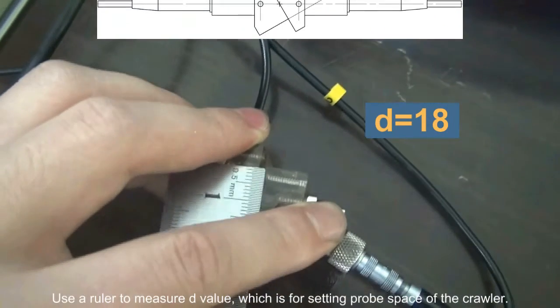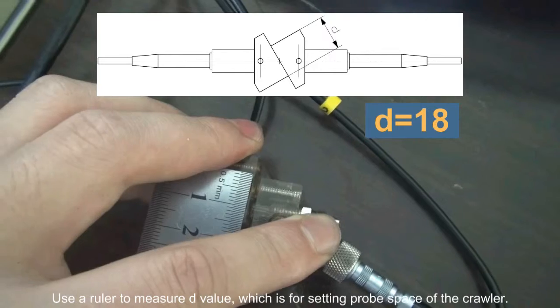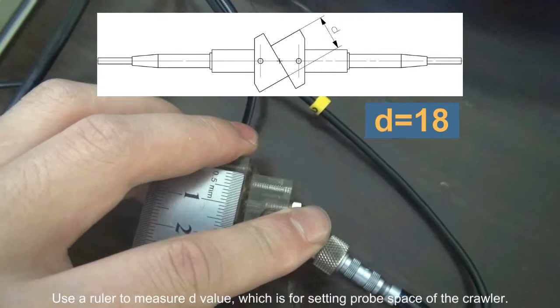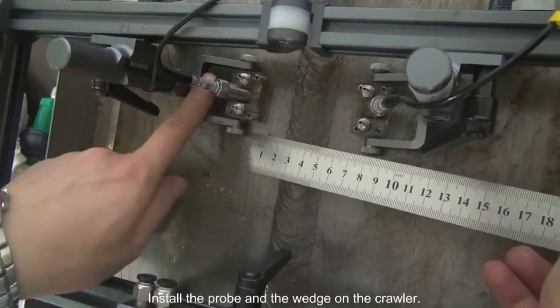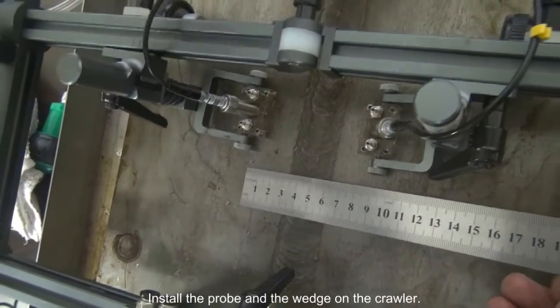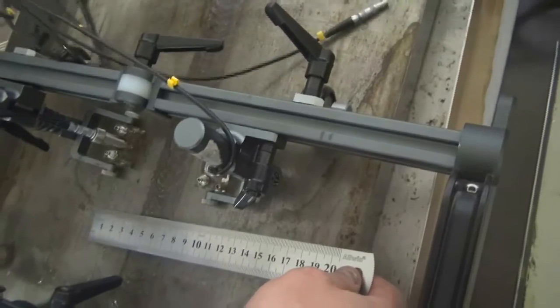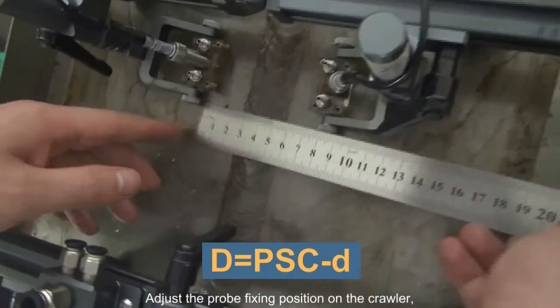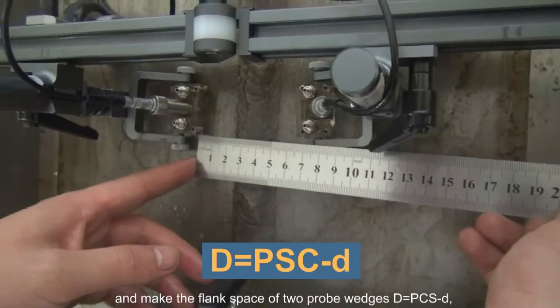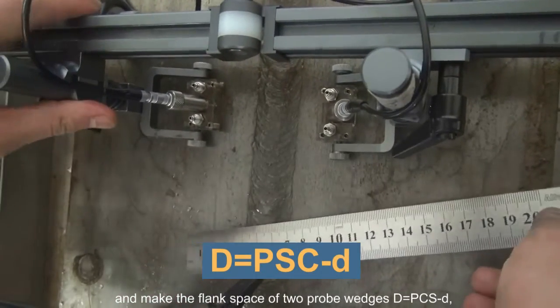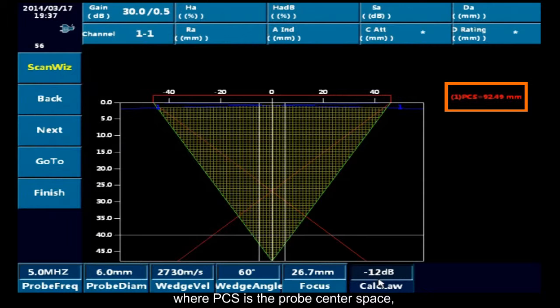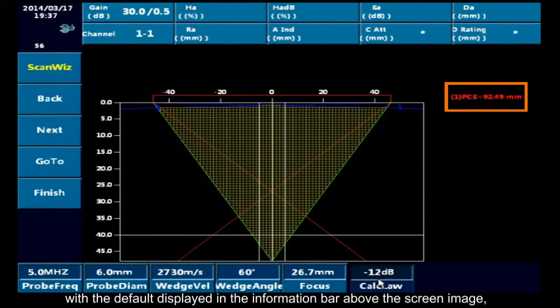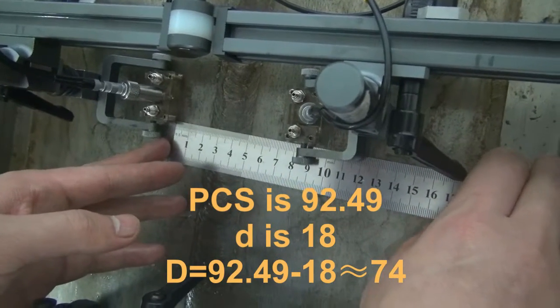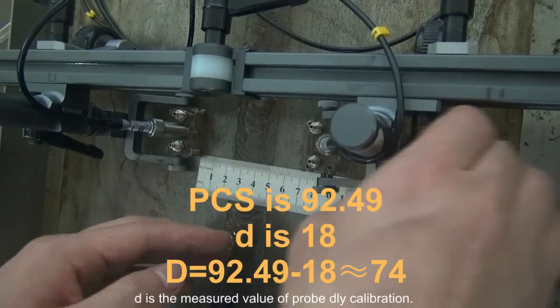Set up crawler probe space. Use the ruler to measure D value, which is for setting probe space of the crawler. Install the probe and the wedge on the crawler. Adjust the probe fixing position on the crawler and make the flank space of two probe wedges D equal to PCS minus D, where PCS is the probe center space, with the default display in the information bar above the screen image. D is the measured value of probe delay calibration.